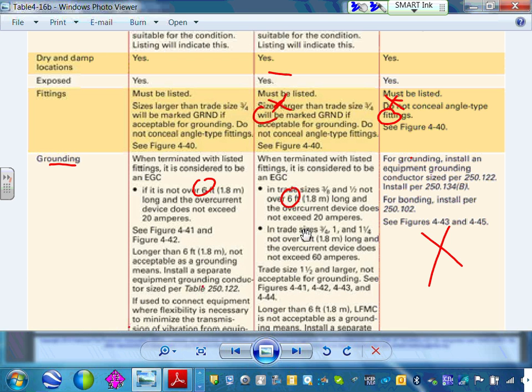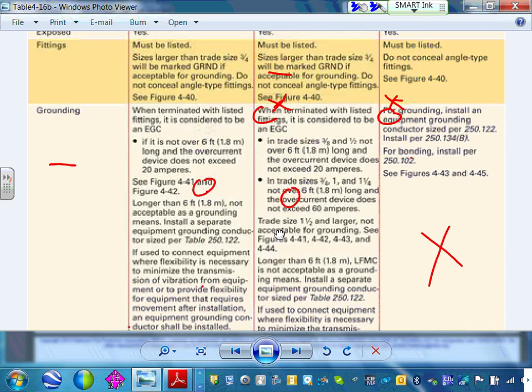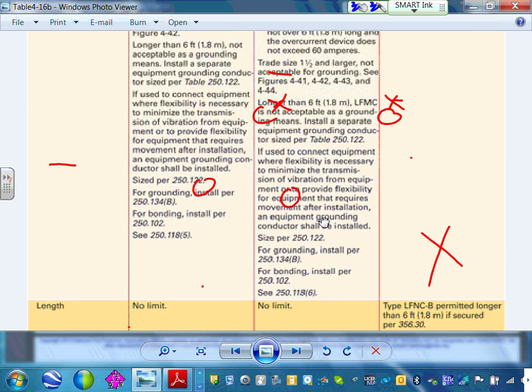And there's also a couple of limitations on the overcurrent protection device ahead of it. So I don't want to go through the whole thing, but the limitation, guys, is you don't need an equipment ground conductor for it when you tie it to a fixture like this. When you tie it to a machine, an air handling unit that vibrates, do you need to put an equipment ground conductor in it? You would hope so, right? Okay, equipment ground conductor. So I want you to remember, the only time these flexible ones don't need an equipment ground conductor is if you tie it to a fixture. Anywhere else, you must have an equipment ground conductor.